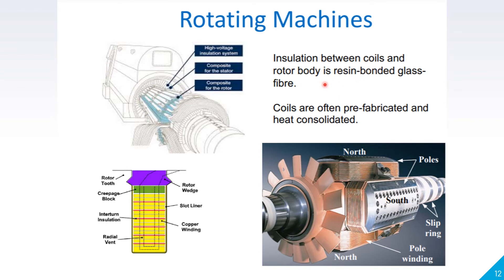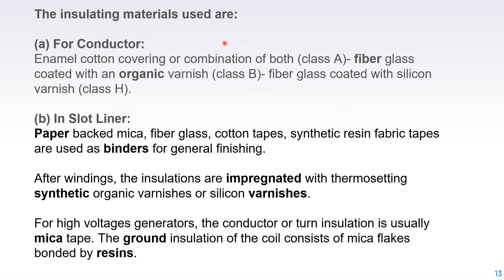Insulation between coils and the rotor body is resin-bonded glass fiber. Coils are often prefabricated and heat consolidated. The insulating materials used for conductors in rotating machines are: enamel, cotton covering, or a combination of both; Class A — fiberglass coated with organic varnish; and Class B — fiberglass coated with silicone varnish. Inside the slot liner, insulation materials used are paper, mica, fiberglass, cotton tape, synthetic resin, and fabric tapes used as binders for general finishing.